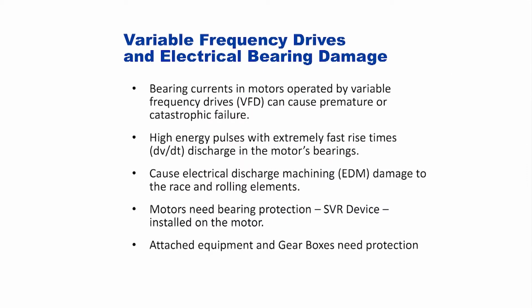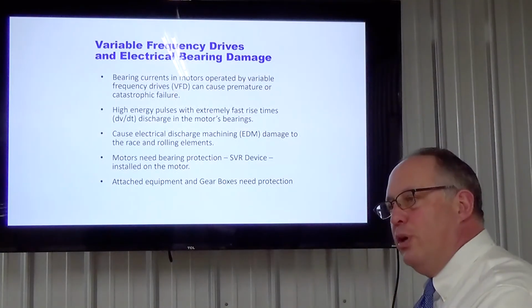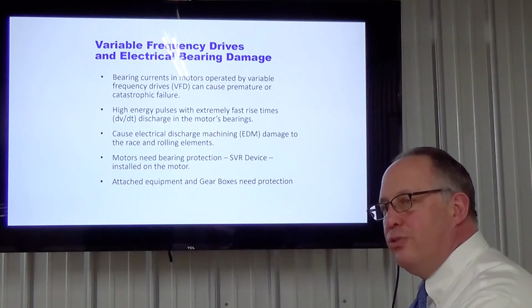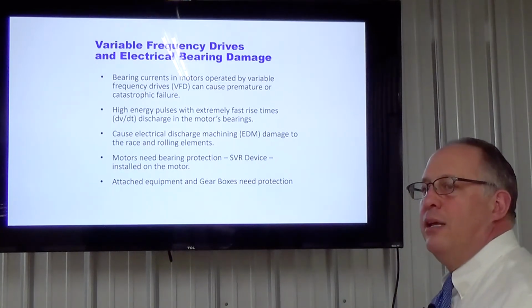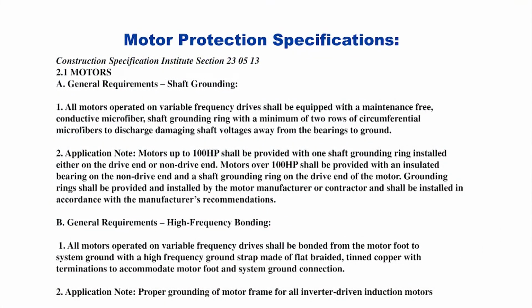Variable frequency drives and electrical bearing damage. Bearing currents in motors operated by variable frequency drive can cause premature or catastrophic failures. High energy pulses with extremely fast rise times, dV/dt, discharge in the motor bearings and can cause electrical discharge machining, EDM, damage to the race and the rolling elements, the balls. The motors need bearing protection with the SVR device, best practice, installed on the motor. Attached equipment and gearboxes need that protection as well. If you put it on the motor internally or at the drive end attached to the frame, that will protect the driven equipment and gearbox.